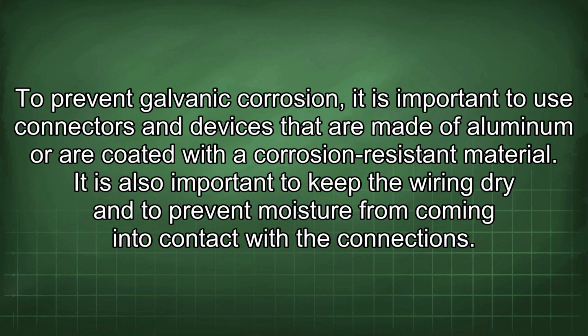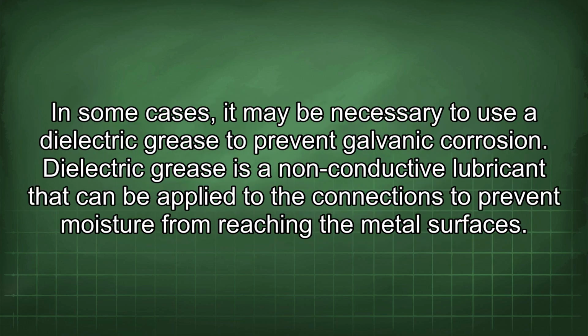To prevent galvanic corrosion, it is important to use connectors and devices that are made of aluminum or are coated with a corrosion-resistant material. It is also important to keep the wiring dry and to prevent moisture from coming into contact with the connections. In some cases, it may be necessary to use a dielectric grease to prevent galvanic corrosion. Dielectric grease is a non-conductive lubricant that can be applied to the connections to prevent moisture from reaching the metal surfaces.